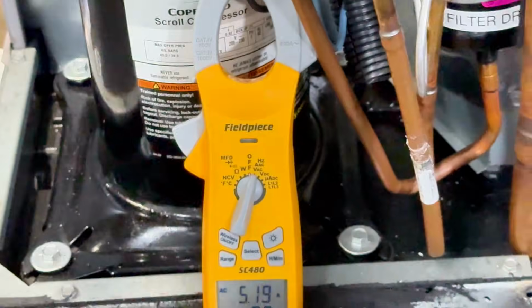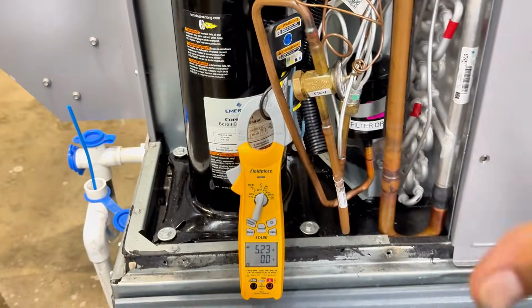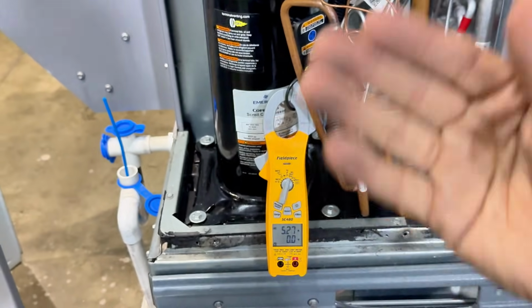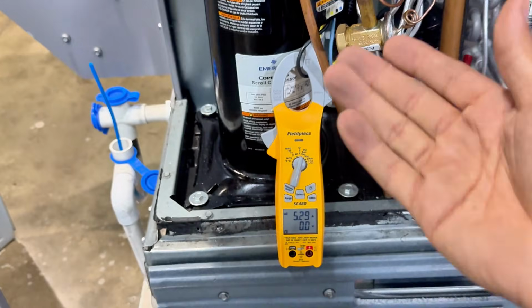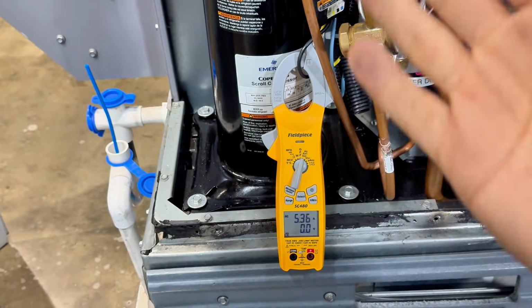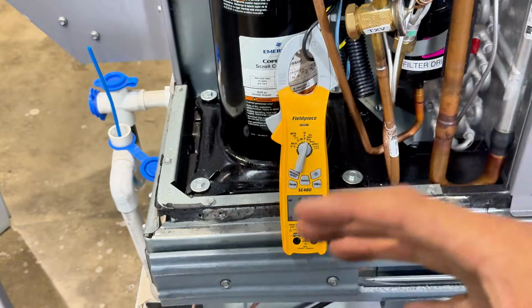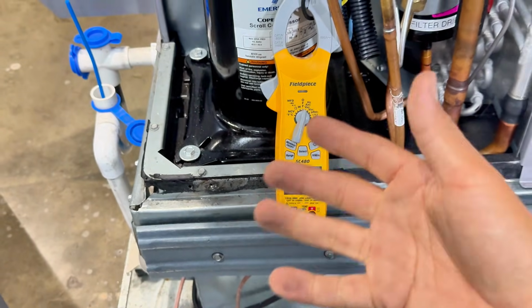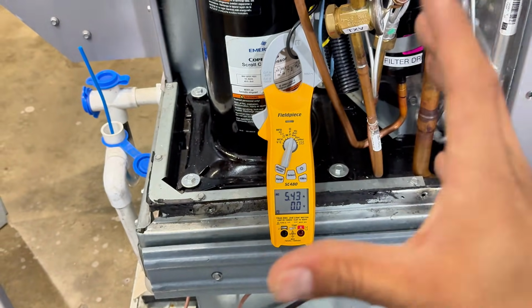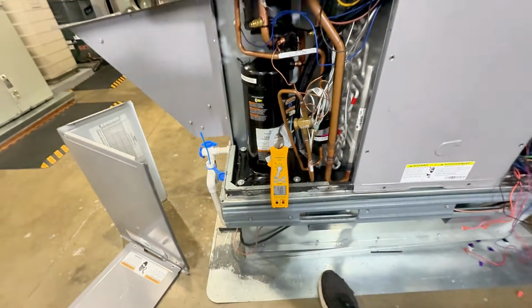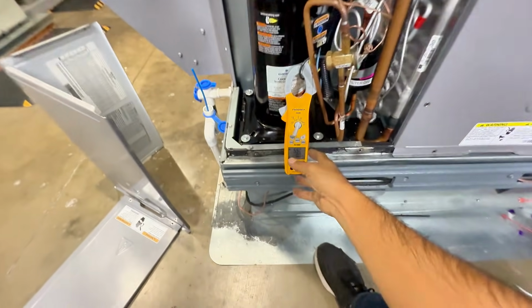Now I'm at 5.1 because I have more heat collected in the refrigeration system. My head pressure goes up, my compression ratio goes up, it's pumping more, working harder, and now you're just wasting energy. But that's what I wanted you to see, by me having a dirty condenser.